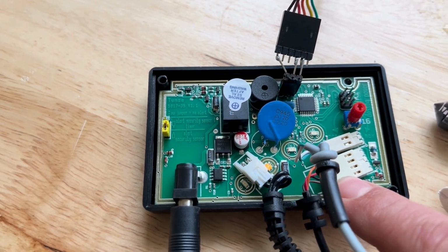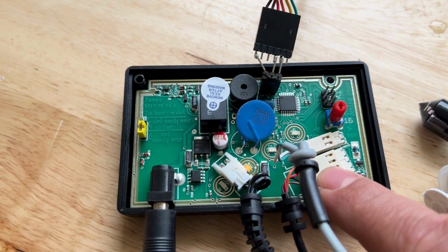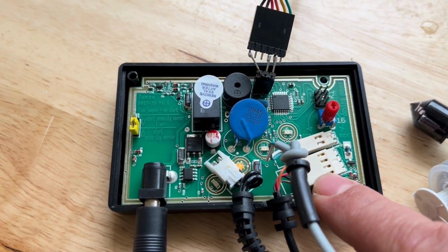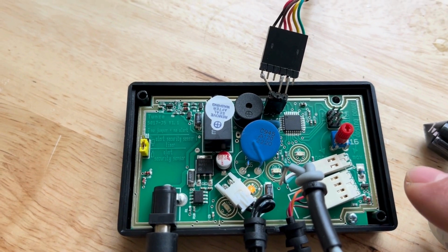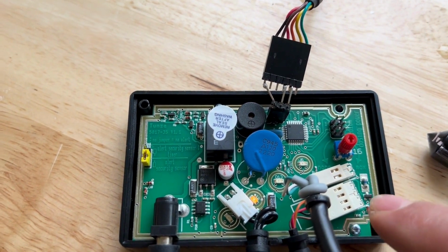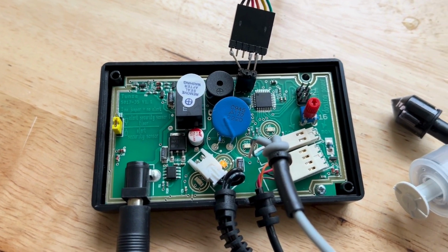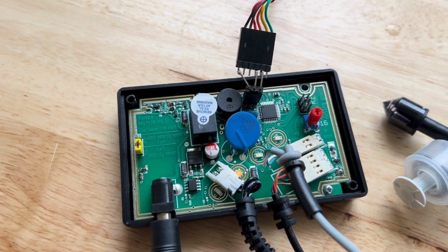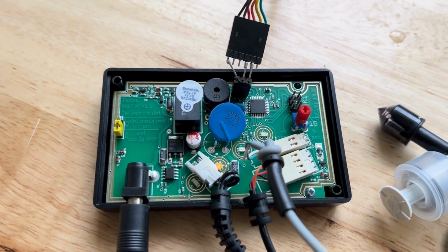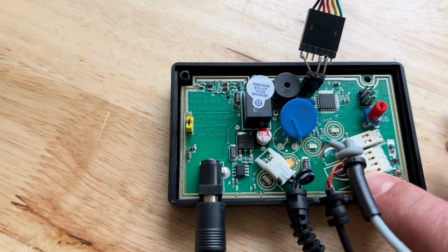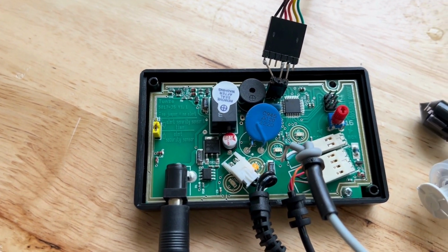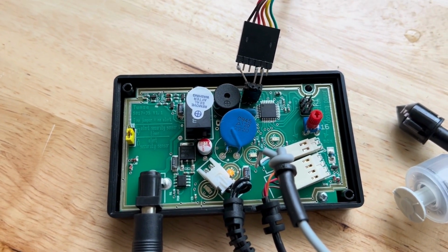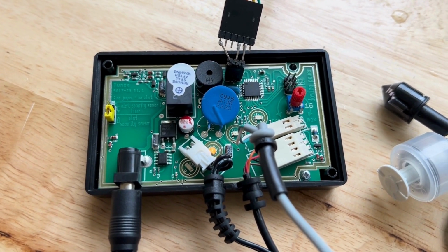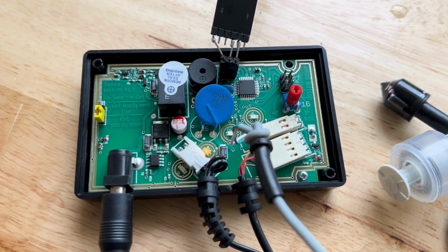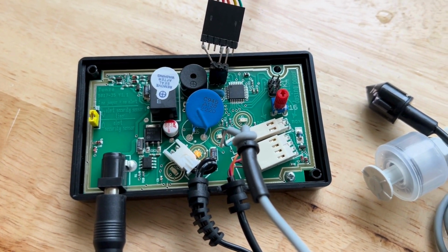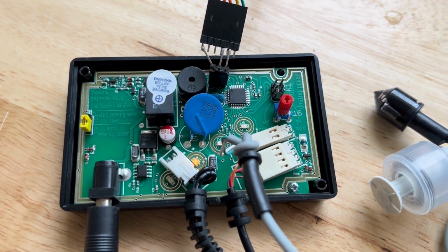While it is not impossible to replace an optic sensor, I strongly advise against it because now we're coming into a unit that's 9 to 10 years old or even older. We're going to see generalized failures of capacitors and different components on the board simply from age. And so it's not often a worthwhile repair. Plus, doing the repair means taking one of these sensors, cutting the plug off. I've essentially ruined the sensor for anyone else's use. And so I have to charge for the sensor even if the repair is unsuccessful, because on these old ones it was soldered in, and I've ruined the sensor to attempt a repair that may or may not be successful.